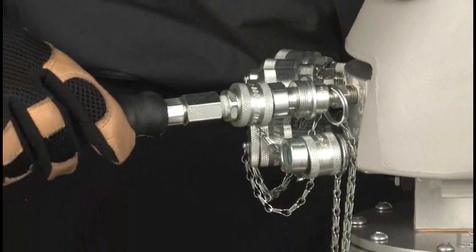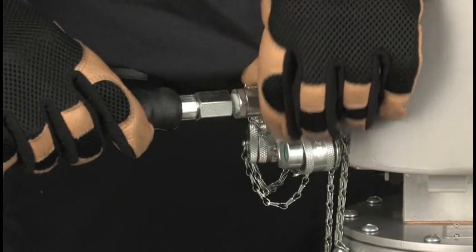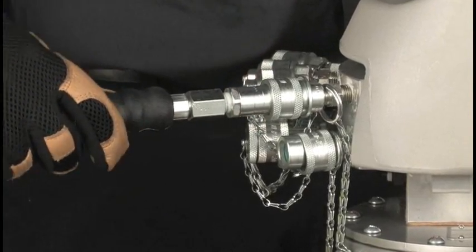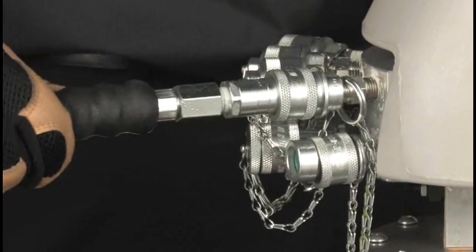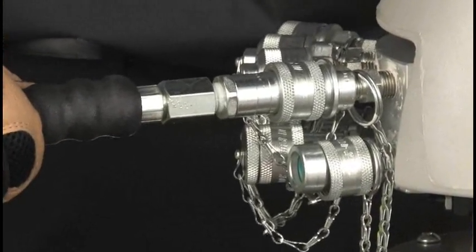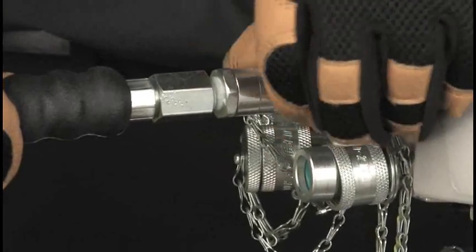The couplers screw together with about three-eighths of an inch thread length, but if they were to loosen even a sixteenth of an inch, the oil would be immediately stopped, protecting the operator from the possibility of a high pressure oil injection. Do not defeat this safety feature by changing or modifying the fittings.